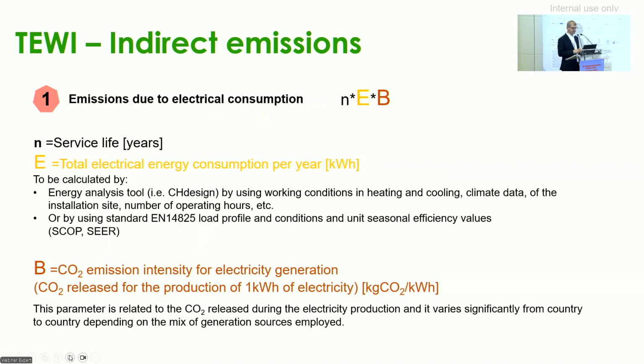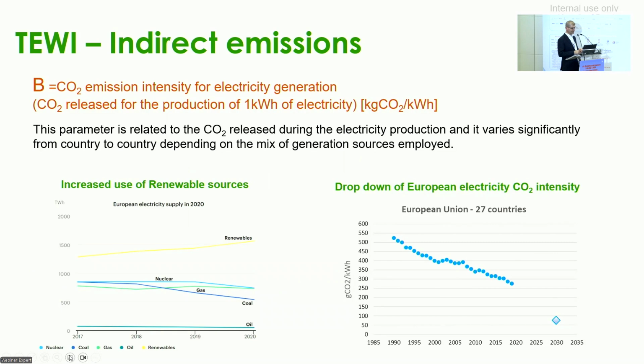The emissions due to the electrical consumption, of course, depend on the service life in years and on the total electrical energy consumed by the unit. This can be calculated in our case with the energy analysis tool made available by the calculation software, or using the seasonal energy efficiency indexes, SCOP for heating and SEER for cooling, together with the EN 14825 load profile. And then there is a coefficient, B, the CO2 emission intensity for electricity generation, that varies from country to country and depends on the specific country's energy policy and the use of renewables.